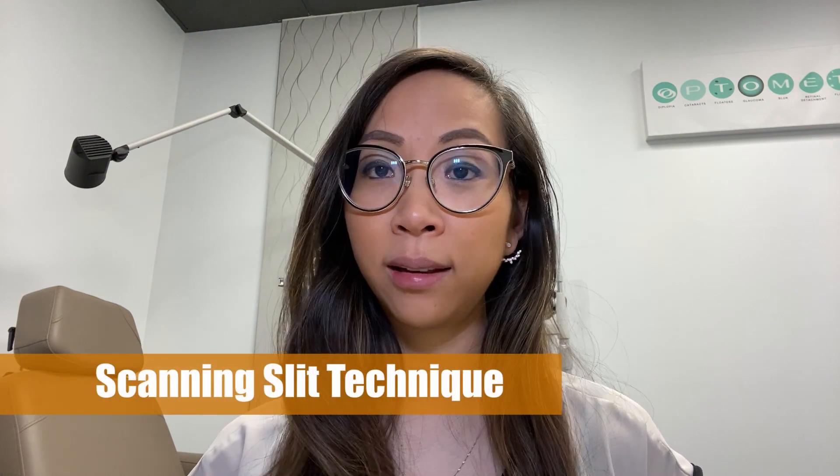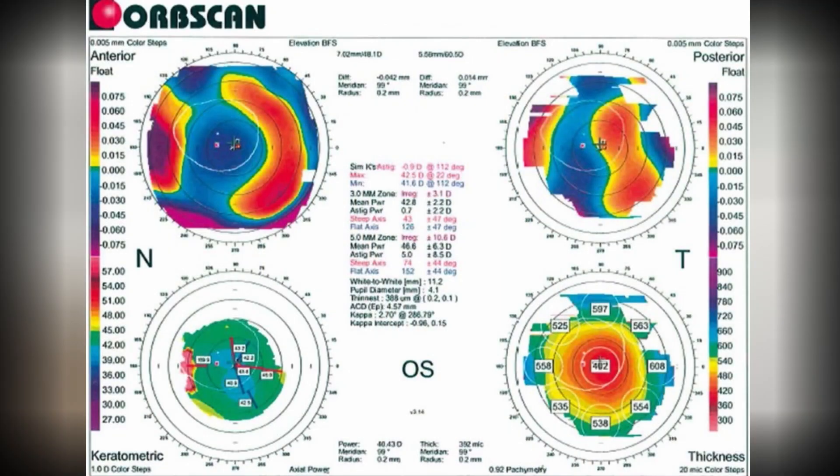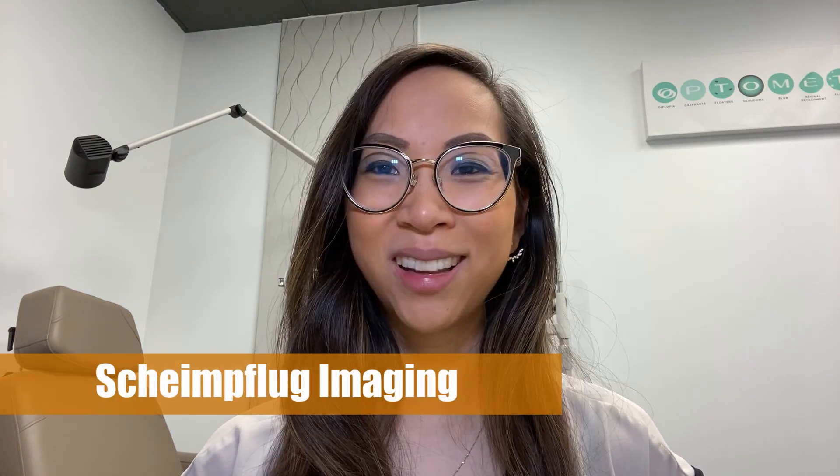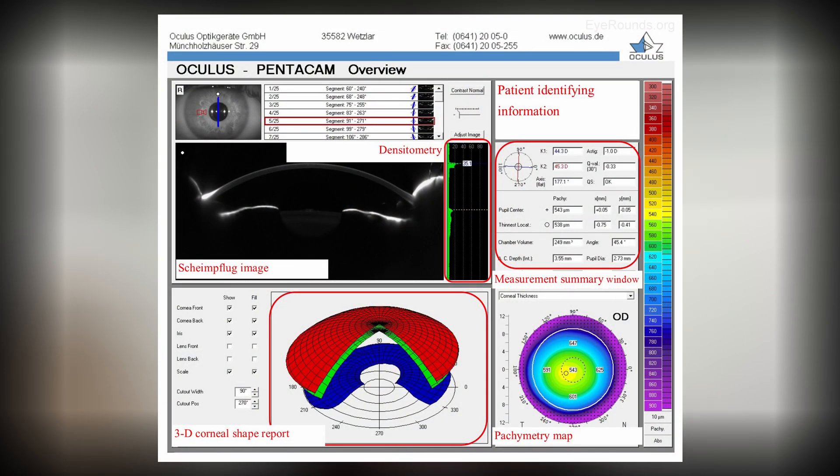This technique provides a very detailed two-dimensional scan of the front surface of the cornea. In order to collect a clear image, the epithelial layer of the cornea in addition to the tear film must be intact. Further advancements now include a scanning slit technique which provides images of both the anterior and the posterior cornea. The newest addition is Scheimpflug imaging, which provides high 3D accuracy and resolution of the cornea — definitely on my wish list for the future.